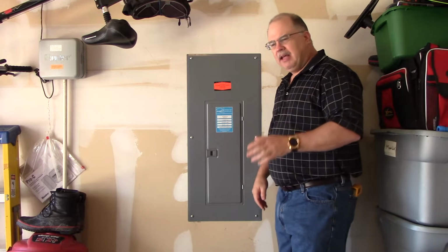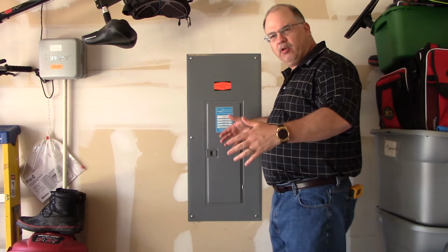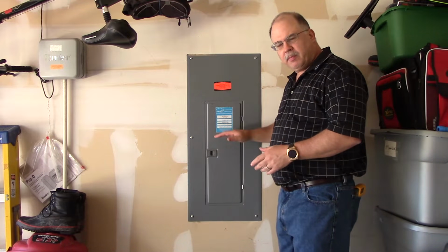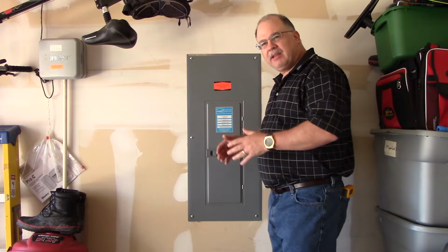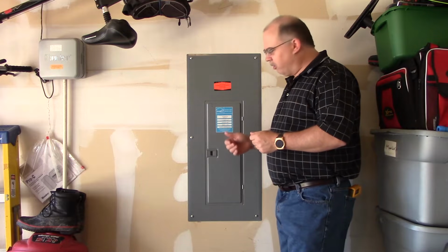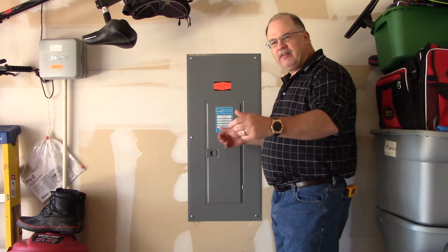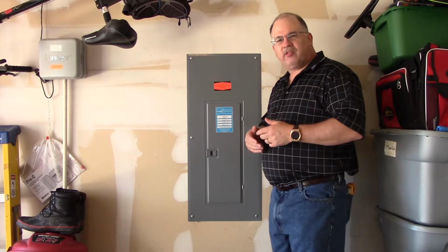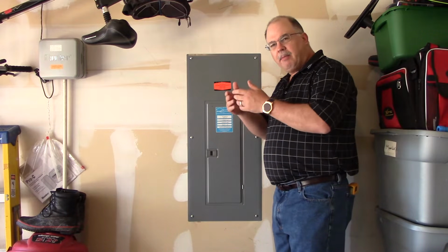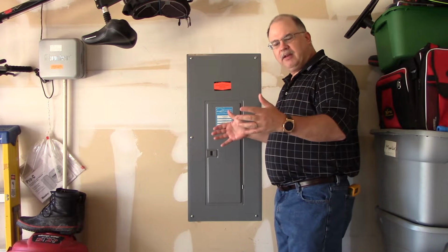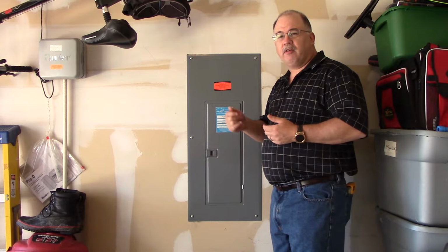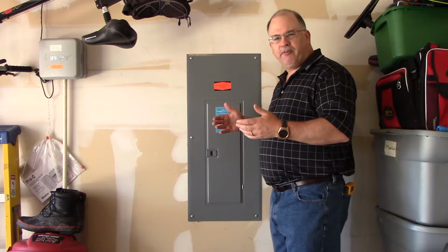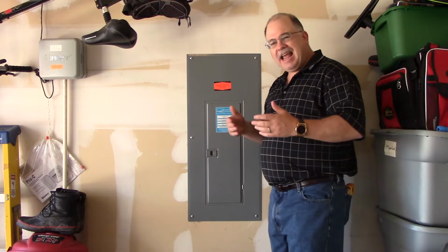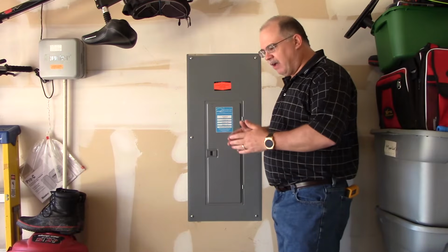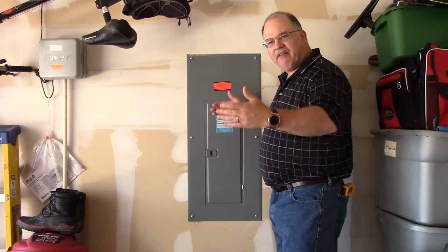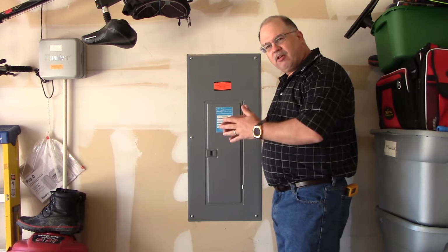The next thing that you want to have is adequate working space in front of this enclosure. You don't want boxes or any tables in front of this, because we need to make sure that we can get to this very quickly without climbing over anything. So in this case here, we want to make sure that we have at least 36 inches or 3 feet. Now, the National Electrical Code says 0 up to 150 volts, nominal 120 to ground, that you need to have 3 feet of clearance. Of course, if it's 150 to 600 volts to ground, it can go between 3 feet all the way up to 4 feet of clearance, depending if you're in a commercial environment, and also depends on certain types of conditions, whether or not you have conductive material opposite of this panel or live parts and what have you. So the depth can change here as far as your clearance is here.